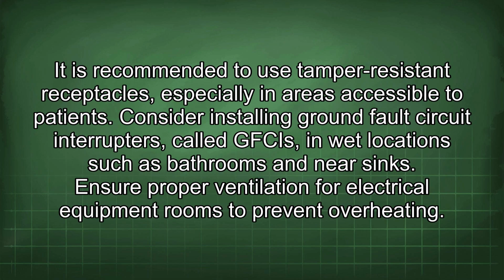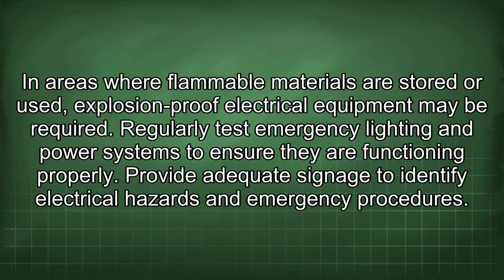It is recommended to use tamper-resistant receptacles, especially in areas accessible to patients. Consider installing ground fault circuit interrupters, called GFCIs, in wet locations such as bathrooms and near sinks. Ensure proper ventilation for electrical equipment rooms to prevent overheating. In areas where flammable materials are stored or used, explosion-proof electrical equipment may be required.